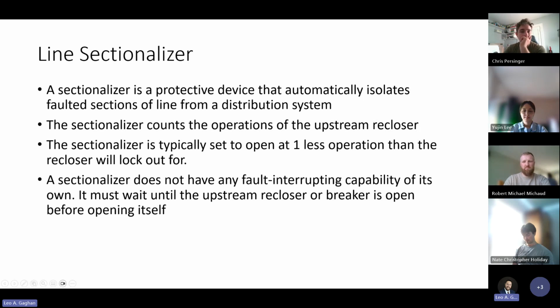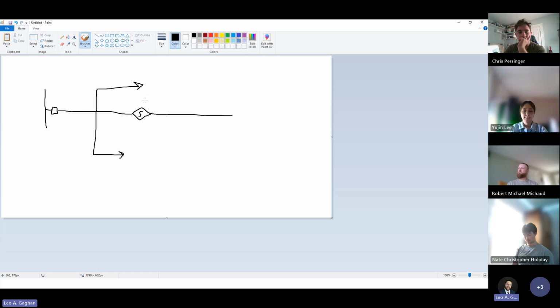So the whole goal for that is, let's say we've got a breaker, call that a sectionalizer, and then we go to a distribution line. And let's say we've got some taps. We don't want those people to lose power. So let's say a fault were to happen right here. This guy is typically set to one less reclose than the upstream breaker. So what would happen is we would have a fault right here. We would have a trip. This guy would count, right? It's not going to be set to interrupt that, but it'll count.